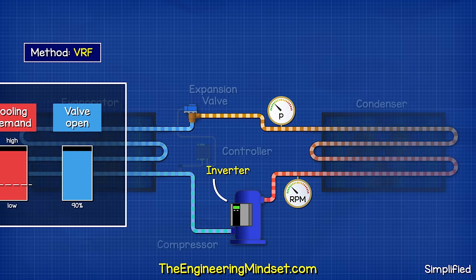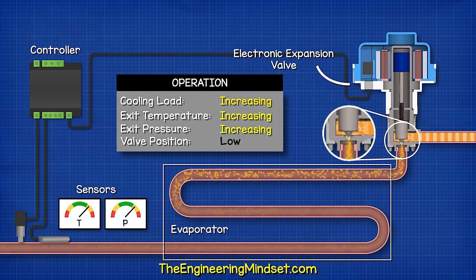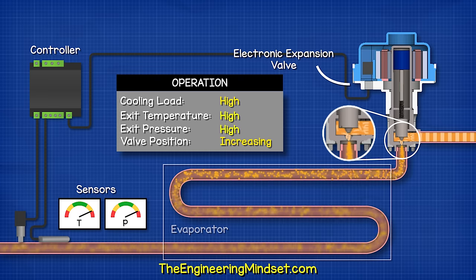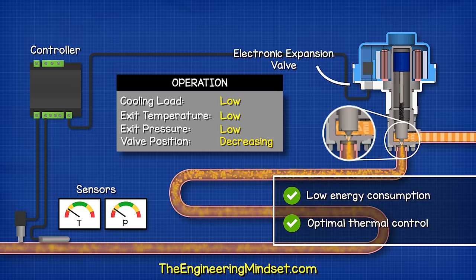Newer designs use a variable frequency drive to control the speed of the motor. And so, the volume of refrigerant flowing around the system changes to match the current cooling demand. This design uses an electronic expansion valve to achieve very precise control. This gives us great energy efficiency and also optimal thermal control.